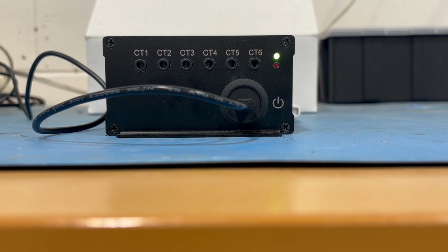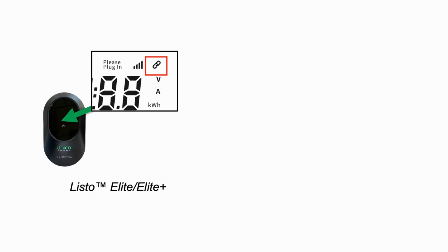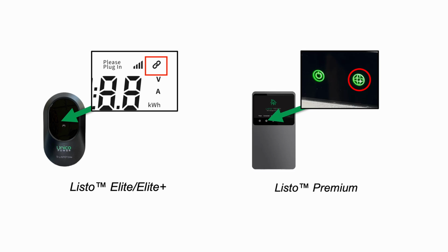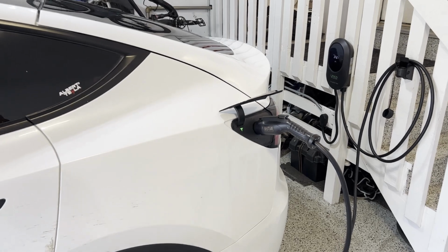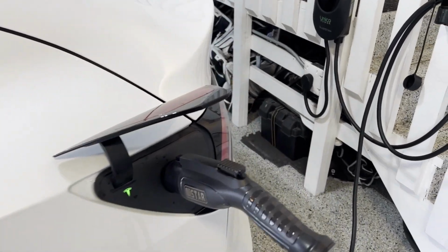Confirm the EMS controller status light is solid green, indicating it's online. On the EVSE, a chain link icon for Elite and Elite Plus, or a globe icon for Listo Premium, will confirm connection. If possible, test charging by plugging into the customer's car.